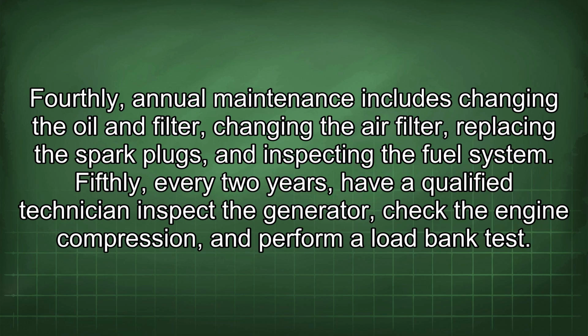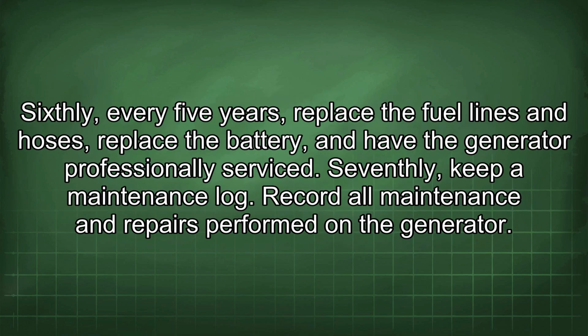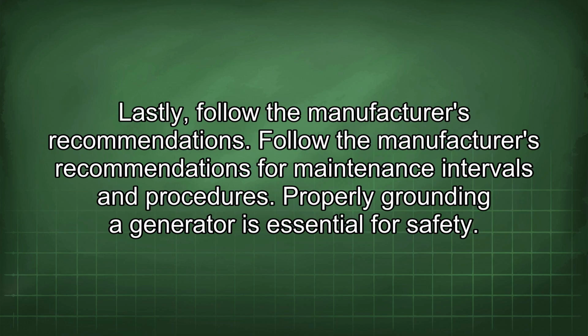Fourthly, annual maintenance includes changing the oil and filter, changing the air filter, replacing the spark plugs, and inspecting the fuel system. Fifthly, every 2 years, have a qualified technician inspect the generator, check the engine compression, and perform a load bank test. Sixthly, every 5 years, replace the fuel lines and hoses, replace the battery, and have the generator professionally serviced. Seventhly, keep a maintenance log. Record all maintenance and repairs performed on the generator. Lastly, follow the manufacturer's recommendations for maintenance intervals and procedures.